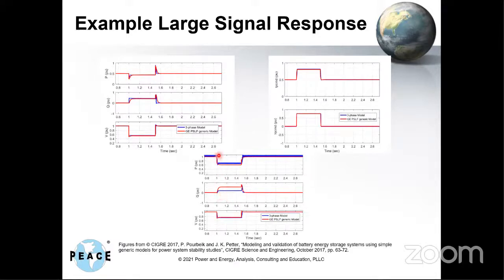What I'm plotting is the positive sequence voltage and the three-phase P and Q. But because it's a positive sequence simulation, it sees this as a positive sequence drop in voltage and gives the appropriate reactive response. Whereas in real life, the EMT controls see that only one phase is dropping, so only that phase responds in Q while the others don't. So there's basically a disparity between the EMT model and the positive sequence model. There are thoughts on using sequence network data to maybe improve positive sequence models to capture some of this, but that's still kind of in the research phase.